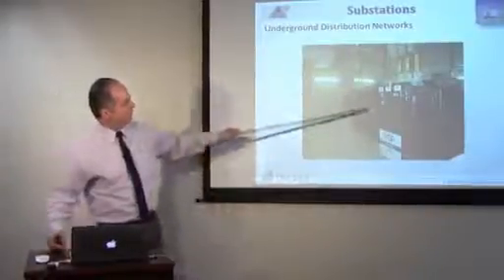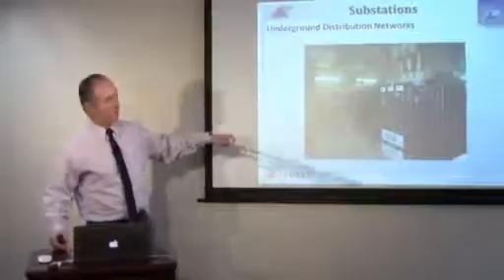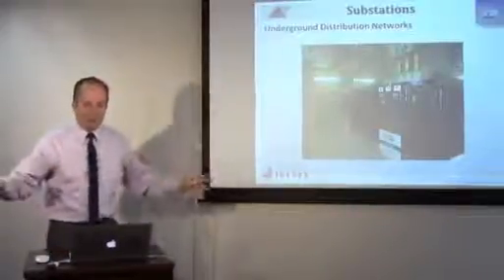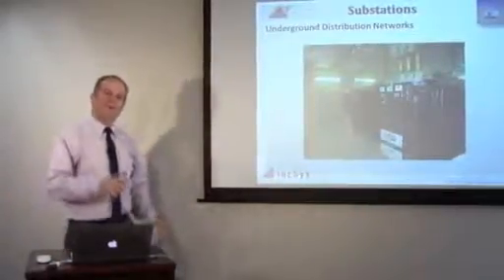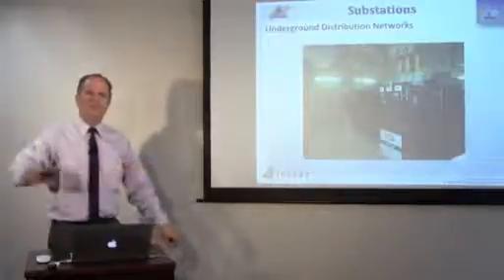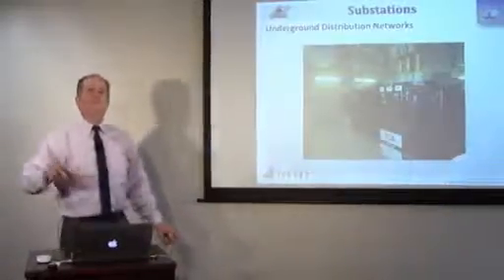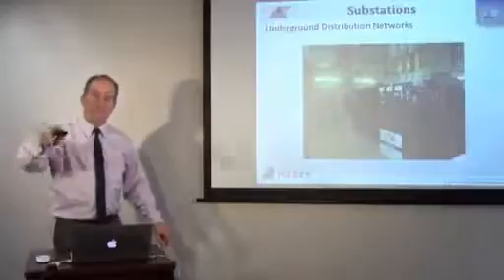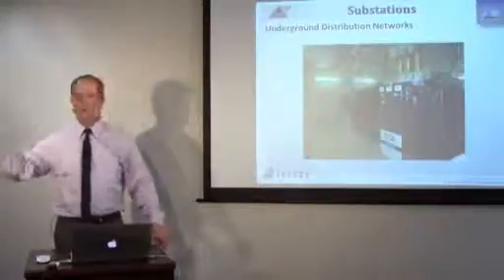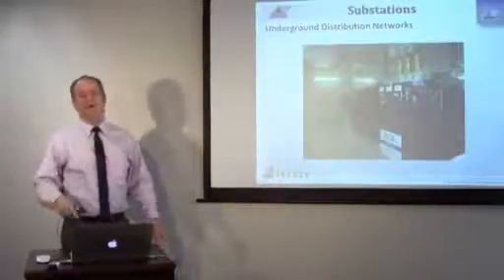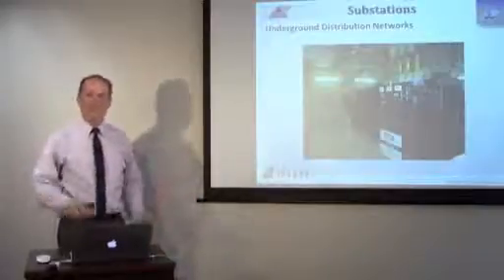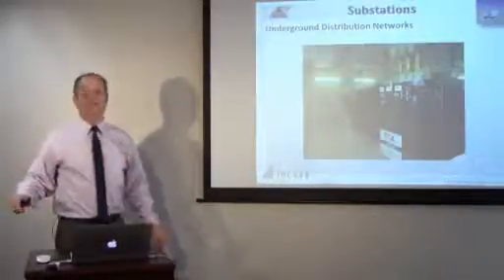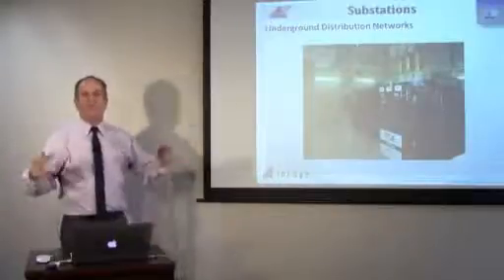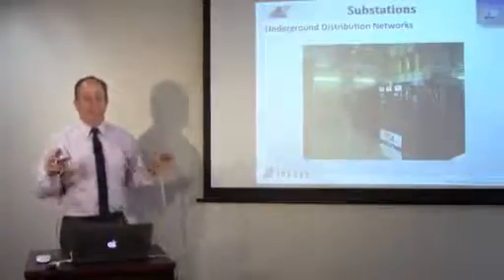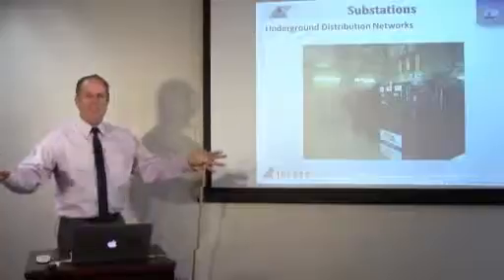But these networks actually parallel transformers, so that 208, 120 three-phase power that's throughout the city streets, when you're hooking up power to a building, you just tap onto that and there's your power. You tap on and go. You don't have a bunch of transformers all over the place. You just have this underground distribution network with all these transformers running in parallel, providing simultaneous power.